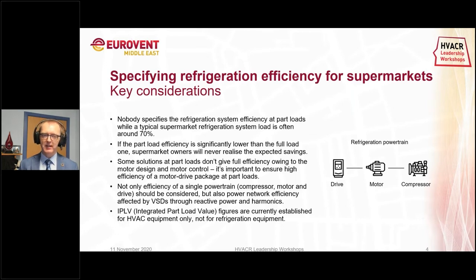We need to look at how we specify in general — not just on the compressors but also on our pumps and fan applications — looking at what the actual load profile of a system is, and then asking manufacturers to provide energy usage estimates over that load profile. The other aspect is that application energy use is not the only inefficiency in the system. Power quality also causes inefficiencies that are not directly reflected in regular energy bills, because your regular energy bill is the active load current — the kilowatt hours you're charged by the utility.